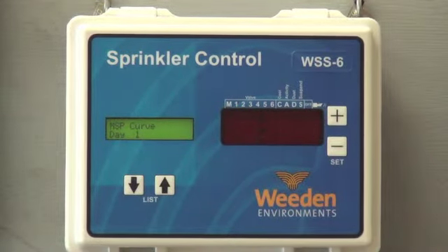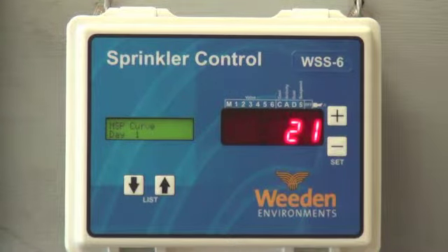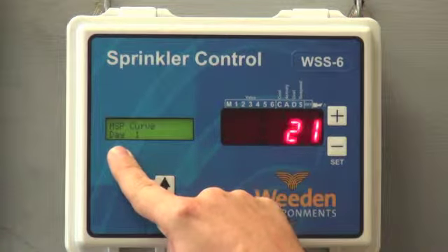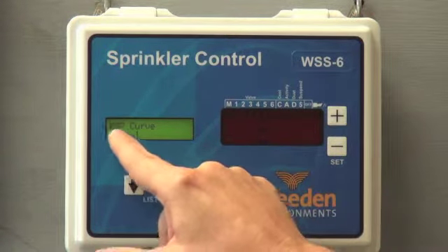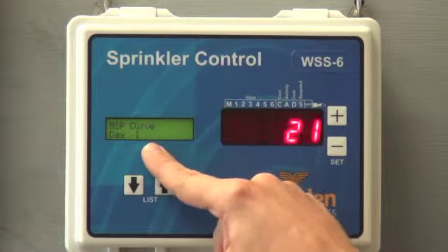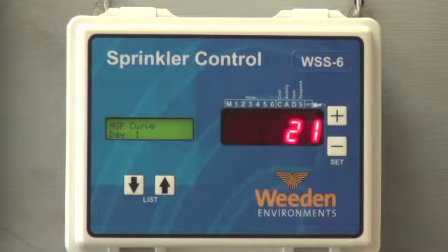I want to tell you that all of this is very nicely explained in our quick setup guide. There's a separate section there that talks about setting up the age temperature growth curve, but it's basically going through the same steps that I'm going to go through right now. You see on the left side of the screen it says day 1 or MSP curve day 1. We actually have 10 different set points that can be put in here, or we can put in a set point at day 1 and a set point towards the end of their life, and the controller will automatically ramp down from day 1 to that point, which is what we're going to do today.